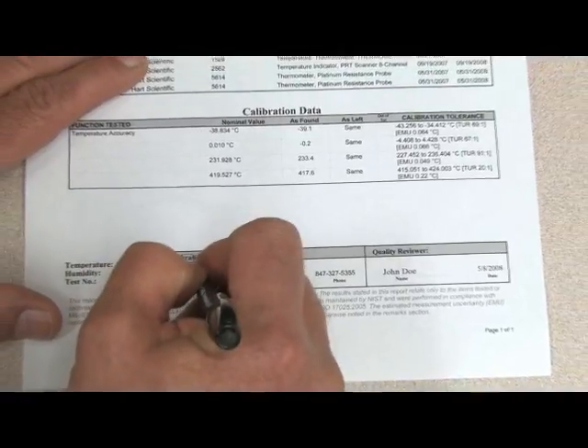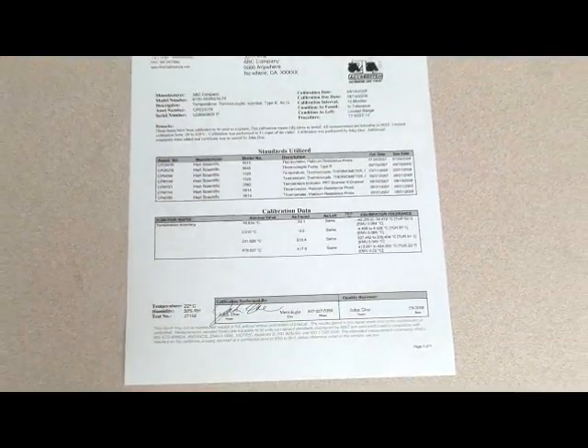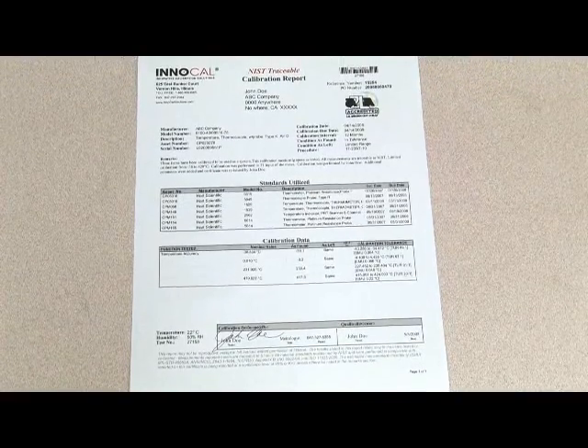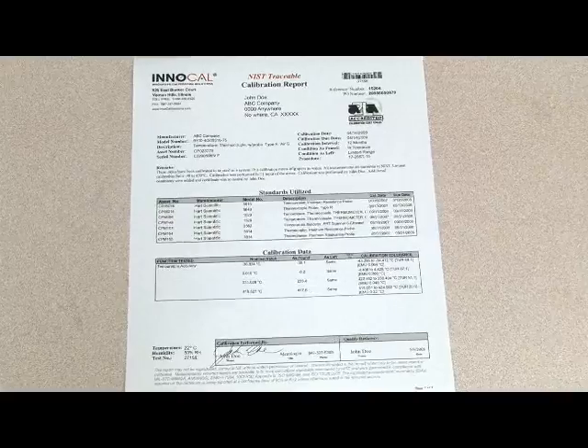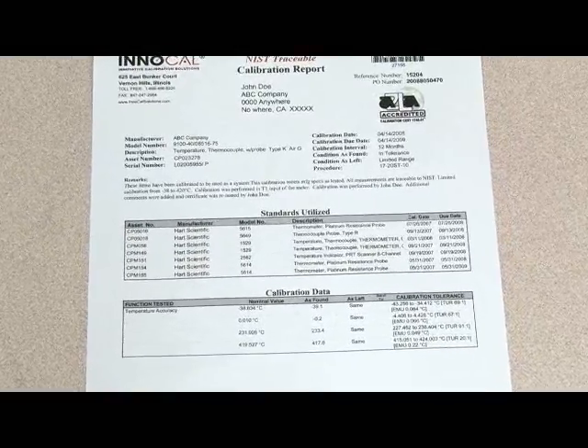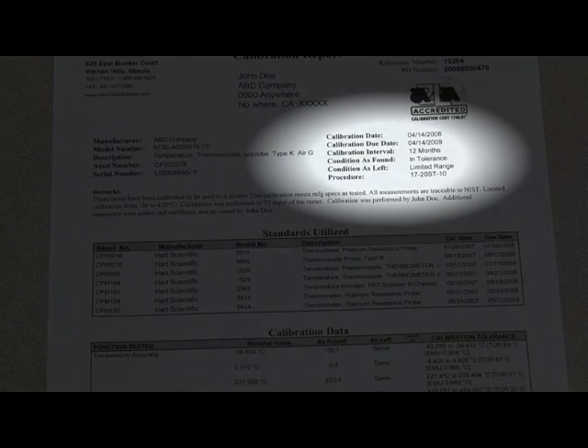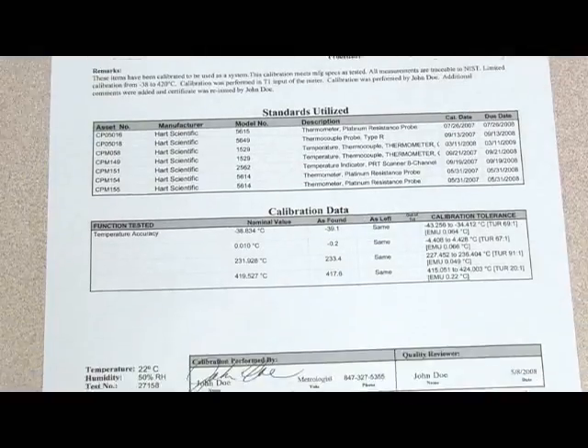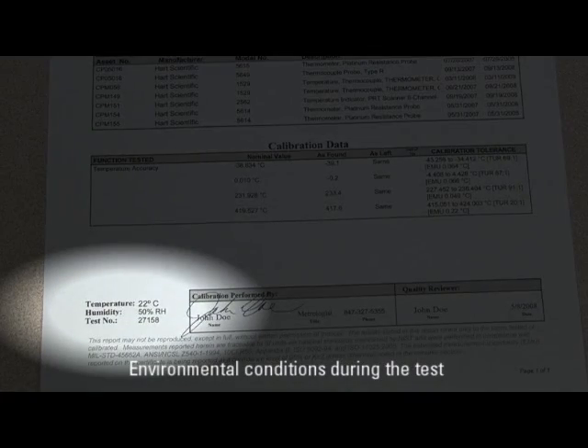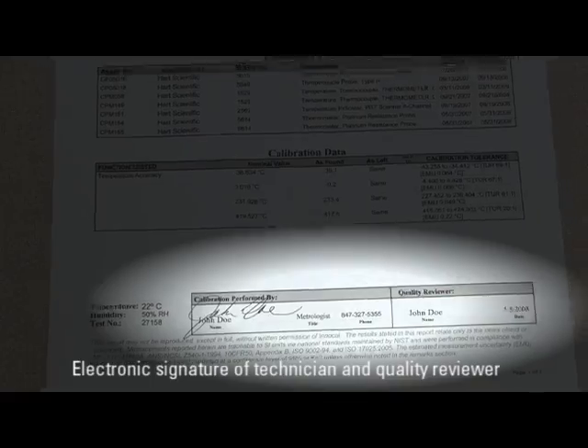INNOCAL's NIST traceable calibration report includes as-found and as-left data, estimated measurement uncertainty, and test uncertainty ratios every time at no additional charge. You'll also see clear identification of the device being tested, condition of the item received, calibration procedure and date, list of standards used, environmental conditions during the test, and electronic signature of the technician and quality reviewer.